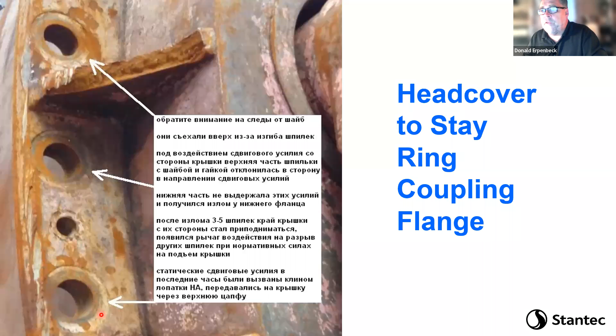And here, by the way, is the head cover flange that failed. Okay, you can see that up here. This was bolted down, and where that thrust cone connects on to the concrete is this flange right here. The flange is not damaged, right? So here's some other pictures of that same area from the other side, right? Here's a damaged wicket gate and that sheared off steel.